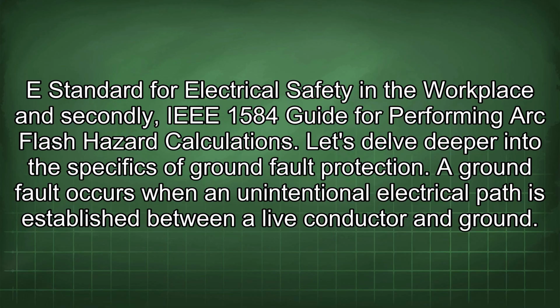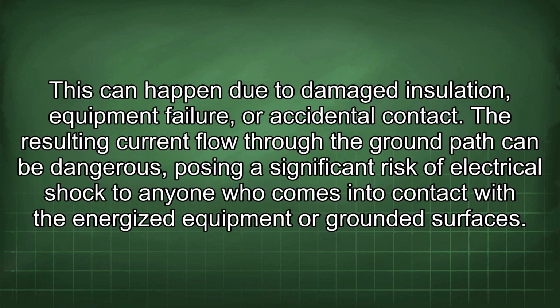Let's delve deeper into the specifics of ground fault protection. A ground fault occurs when an unintentional electrical path is established between a live conductor and ground. This can happen due to damaged insulation, equipment failure, or accidental contact. The resulting current flow through the ground path can be dangerous, posing a significant risk of electrical shock to anyone who comes into contact with the energized equipment or grounded surfaces.